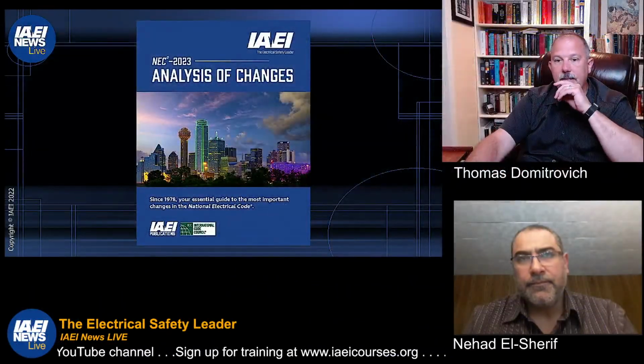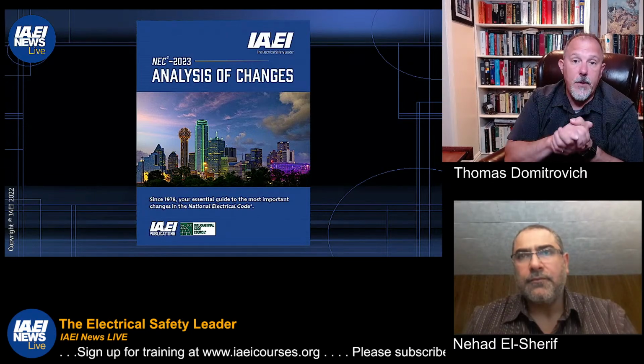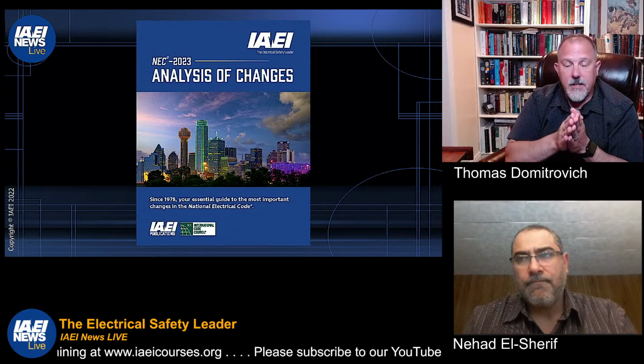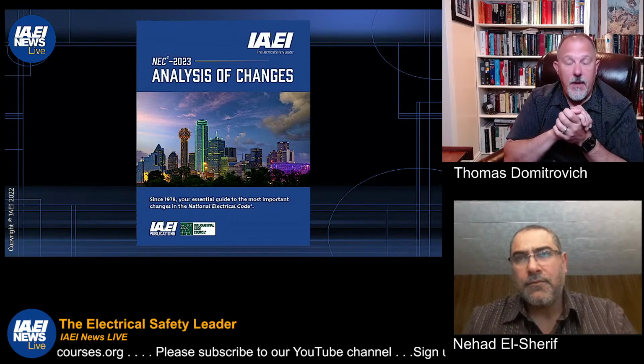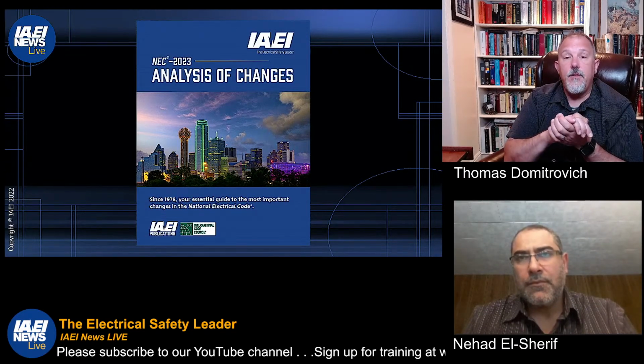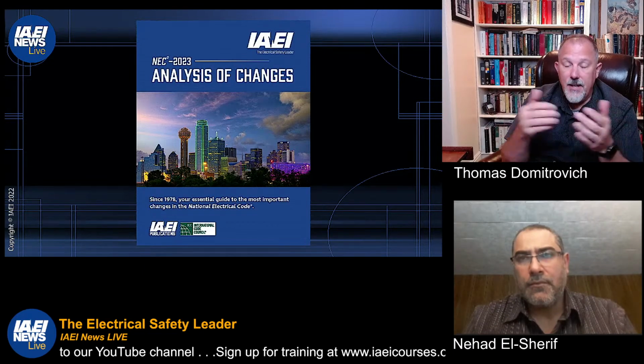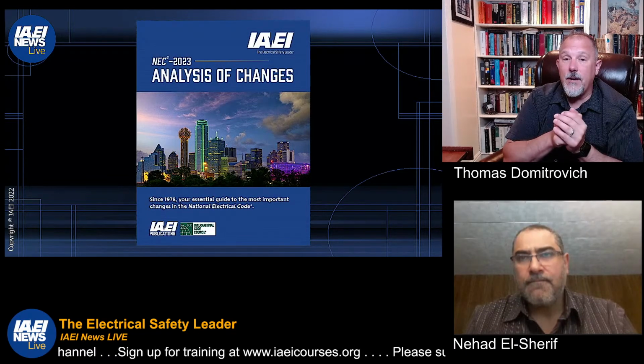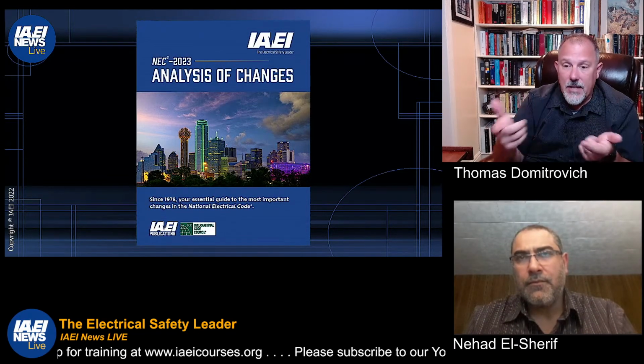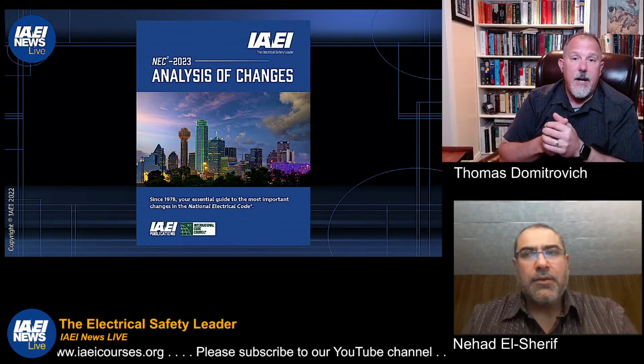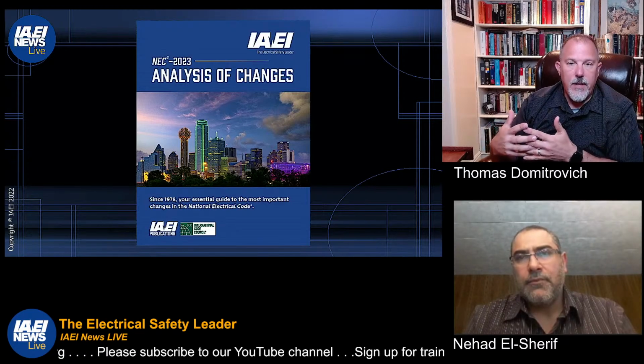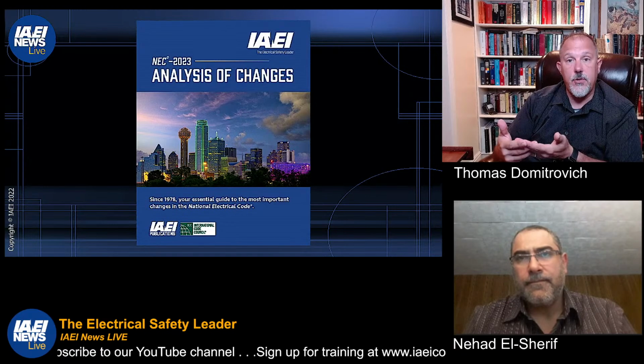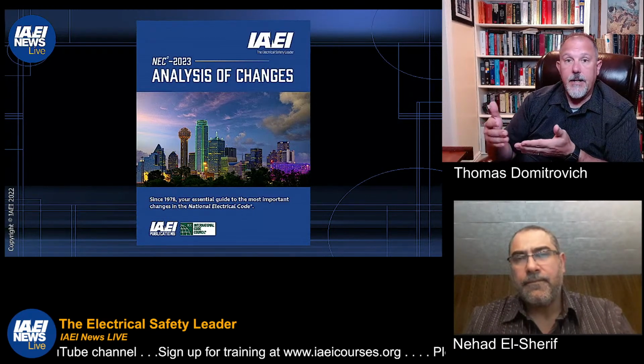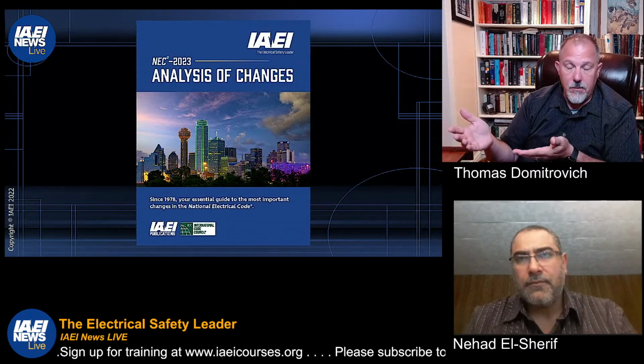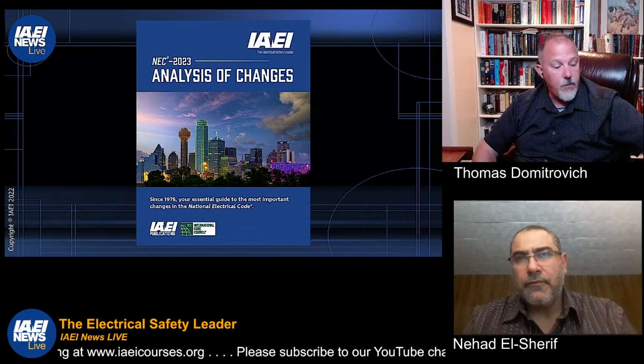Where's it at? Hold on. In the IAEI's analysis of changes, which you can pre-order right now. The analysis of changes will include the specific areas within Article 680 that now require the use of a special purpose GFCI, which is the stimulus for this discussion. When the National Electrical Code starts to require a technology that is new, I wouldn't say it's new, Nehad, right? The special purpose has been around, but it will be new for the NEC. And so it's important for us as electrical professionals who have to follow the National Electrical Code, and in areas where you might want to exceed it, to understand the technologies that are out there and the correct way for proper use.